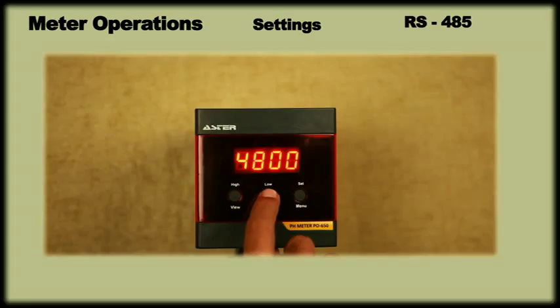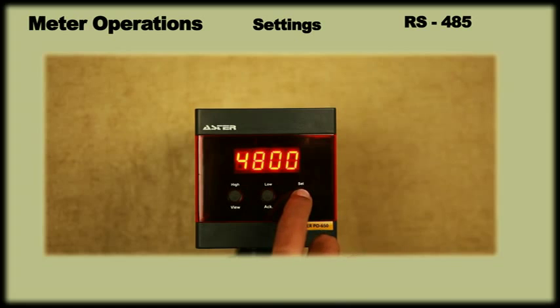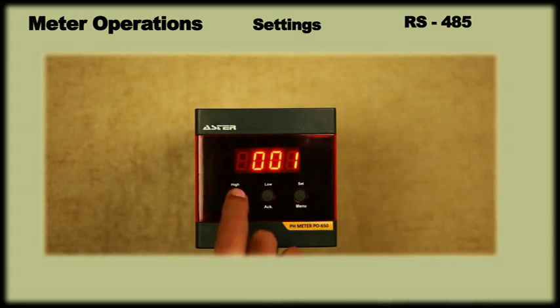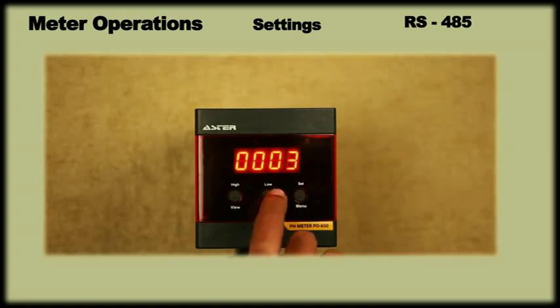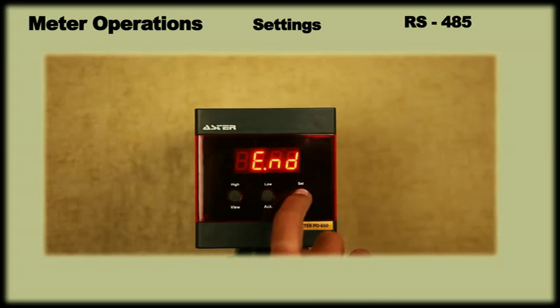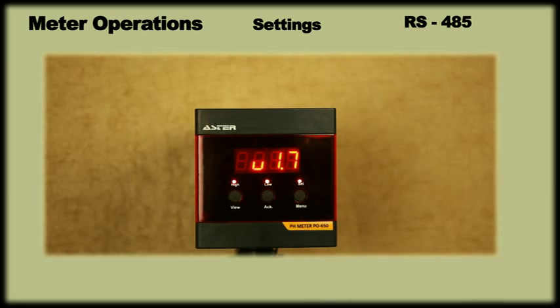Once you have selected the desired baud rate, press menu twice and the display will ask for device address. Use the View and ACK key to set the device address to the required address. Press menu twice to save and exit. The maximum number of device address settable is 25.